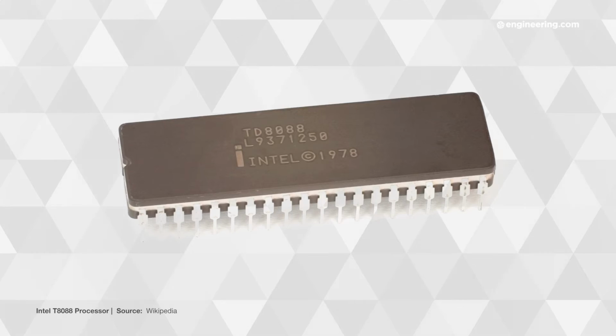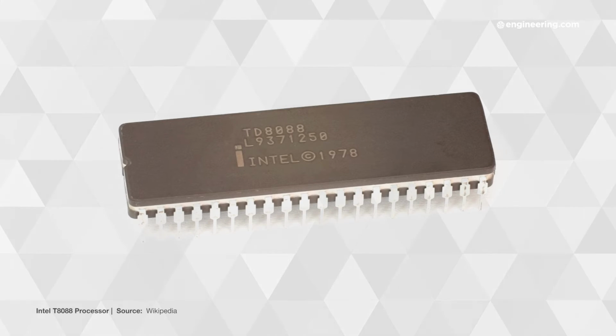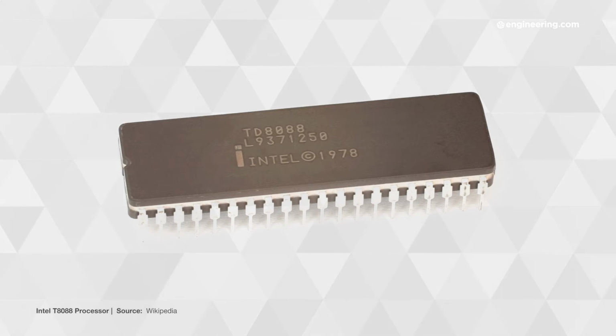A couple of decades ago, I would instinctively suspect an 8088 processor in a motherboard as the culprit in an automation application, for example. With today's much more sophisticated systems, however, a semiconductor power device or a short circuit or open ground are far more likely to cause a circuit failure. Now, this doesn't require a PhD to cope with. And for anything over about 5 amps, these devices make troubleshooting literally a snap. I hope they never go away.